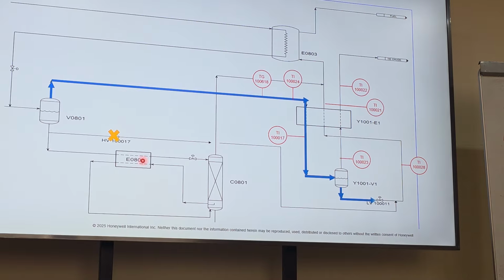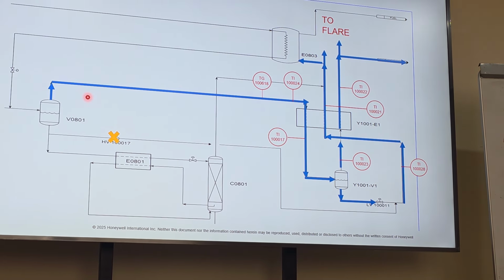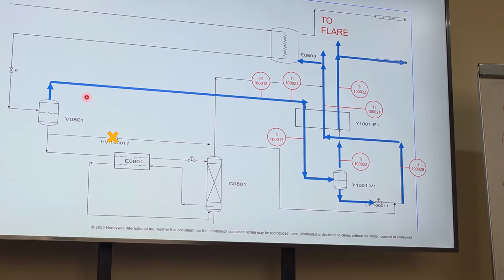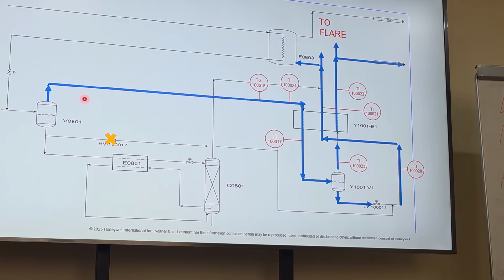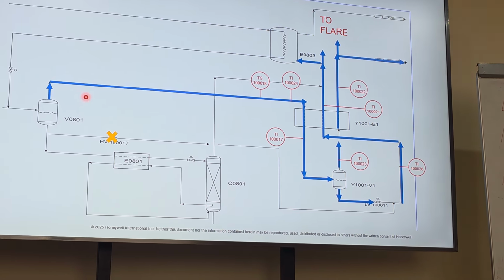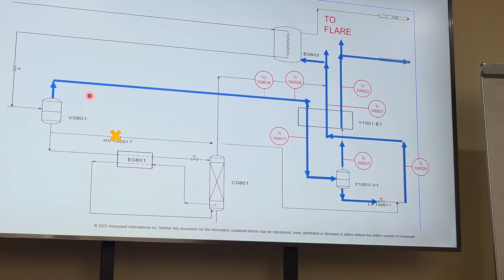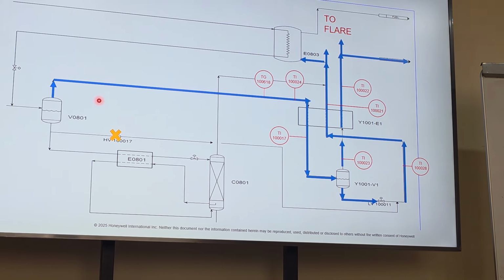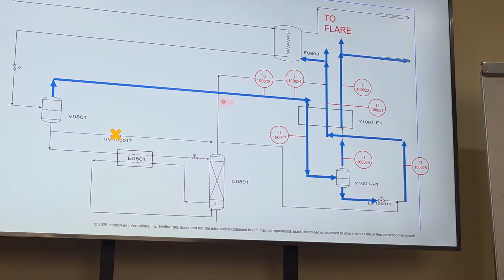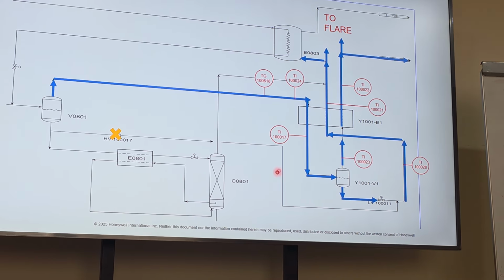By integrated, this is basically just saying you start up and you want to cool everything down at once. Say you're trying to cool down unit 8. You can cool down unit 10 with unit 8. Personally, I think that's easier. That is the best, and it's also less risky, because now all of the equipment is getting cold together, so the chance of delta T's being different is lower. Once again, you're starting up unit 8 and you want to cool it down, starting it warm. As you begin cooling this down, open this up to the helium recovery unit and begin that cool down.